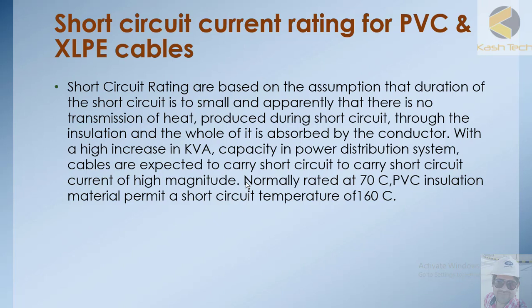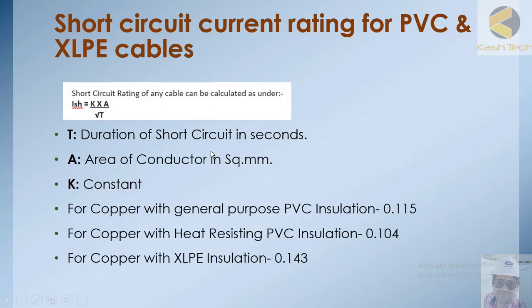PVC insulation, normally rated at 70°C, permits a short circuit temperature of 160°C. The short circuit current of any cable is calculated as: I_sc = k × A / √t, where t is the duration of the short circuit in seconds and A is the area of the conductor in mm². The constant k is 0.115 for copper with general PVC insulation, 0.104 for copper with heat-resistant PVC, and 0.143 for copper with XLPE insulation.